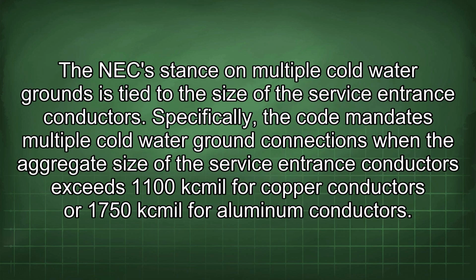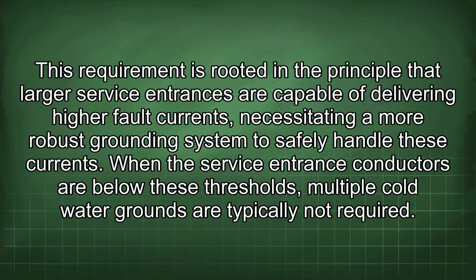The NEC stance on multiple cold water grounds is tied to the size of the service entrance conductors. Specifically, the code mandates multiple cold water ground connections when the aggregate size of the service entrance conductors exceeds 1100 kcmil for copper conductors or 1750 kcmil for aluminum conductors. This requirement is rooted in the principle that larger service entrances are capable of delivering higher fault currents, necessitating a more robust grounding system to safely handle these currents.